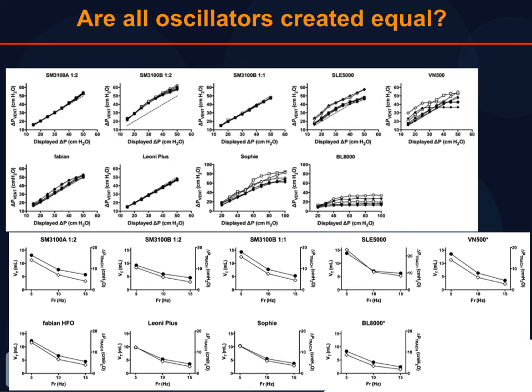So what we've been interested in, the initial question we asked was, well, if we set a delta P, what delta P does the device actually give? And that came about because of this knowledge that the way you could set delta P on the Sensormedics was different from the way you could do it on the BabyLog. And again, it doesn't mean one device is better or worse than another, it just means that you drive it differently. And the user needs to understand that.